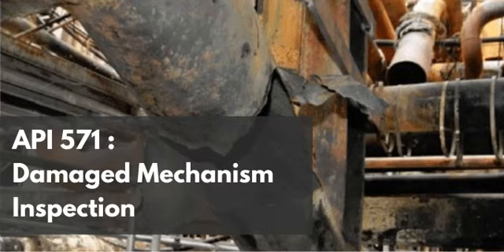That is incredible technology. Okay, now for carbon steel, we are dealing with a magnetic material, and we are looking at massive welds on tanks and piping, not tiny tubes. What is the NDE approach there? Well, for carbon steel, the focus is entirely on interrogating the non-stress-relieved welds and their associated heat-affected zones. Because the steel is magnetic, inspectors utilize techniques like wet fluorescent magnetic particle testing, or WFMT, for surface cracks.